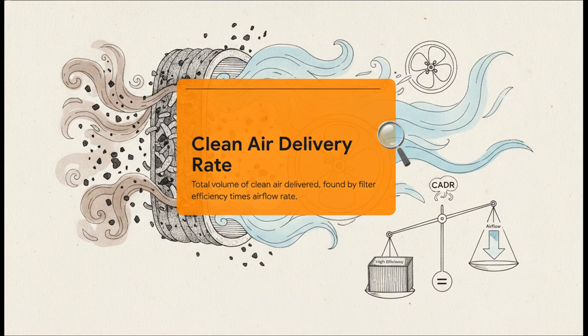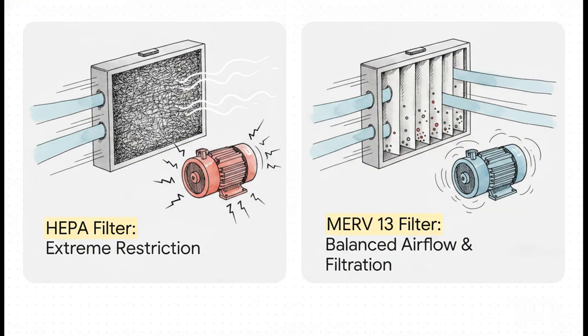If you use a filter with extremely dense fibers, sure, it catches more particles, but it simultaneously restricts the total volume of air flowing through your system. When you're choosing between HEPA and MERV 13, that CADR equation changes everything. HEPA filters offer extreme filtration efficiency for ultra-fine particles, absolutely. But because they are so incredibly dense, they are highly restrictive to airflow. If you slap a HEPA filter into an average home HVAC system, you will overstrain the blower motor and drastically reduce your total CADR. HEPA is really best reserved for localized, small-volume purification.